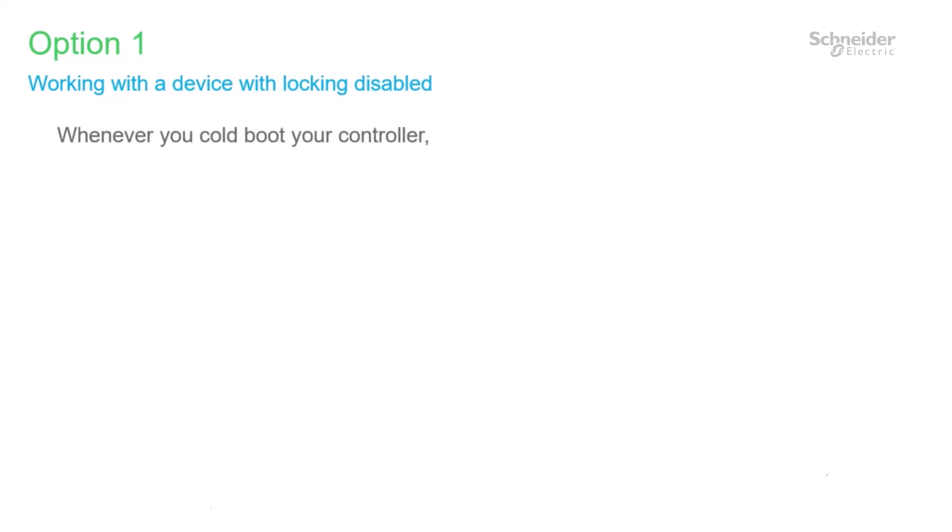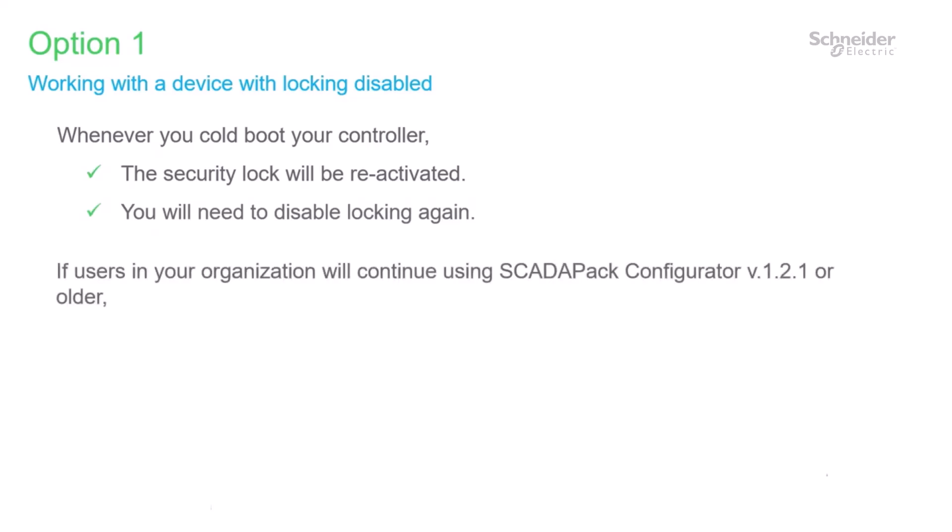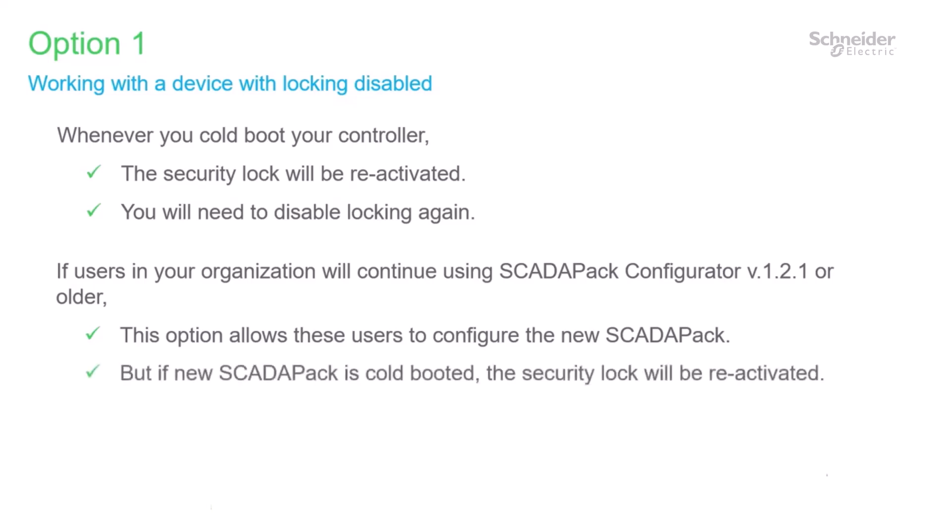Now with locking disabled, I'd like to point out a few items when working with a device with locking disabled. In the future, if you need to cold boot your controller, note that the security lock will be reactivated and you will need to disable locking again as just shown. If you have users in your organization that intend to remain using SCADAPack Configurator 1.2.1 or older, then disabling the security lock also allows these users to configure the RTU without issue. However, if one of these users needs to cold boot the controller, the security lock will be reactivated and only SCADAPack Configurator 1.3.1 or newer can disable locking at this point. All the more reason to have all your users update their PCs with the latest version of SCADAPack Configurator.